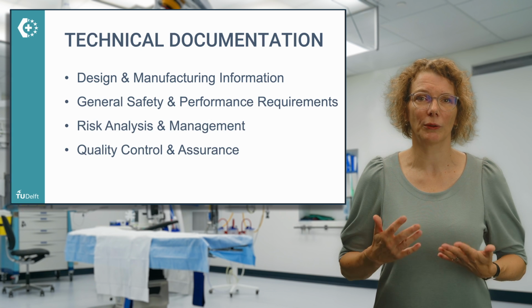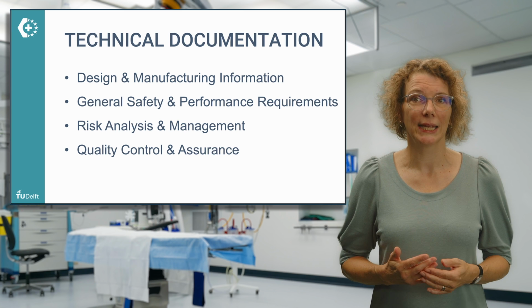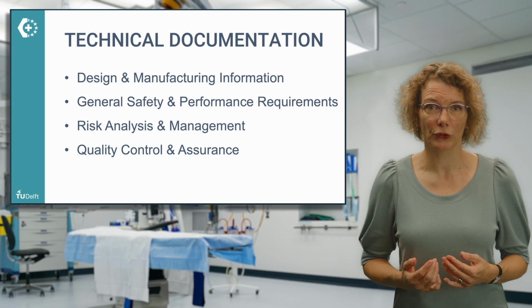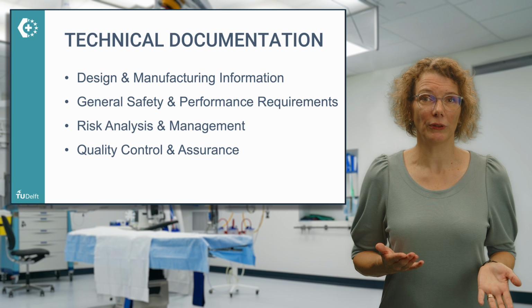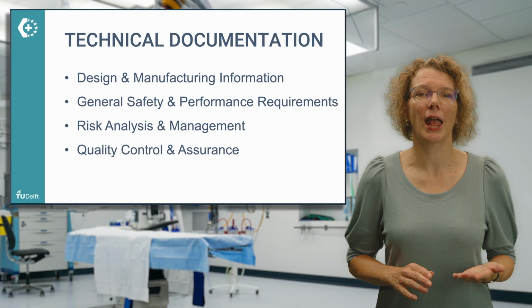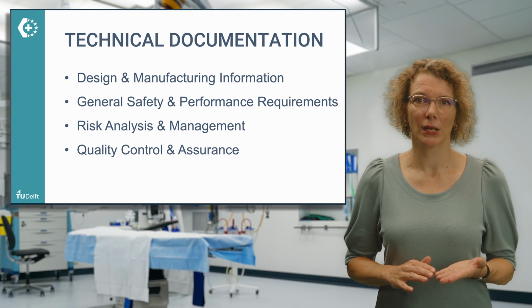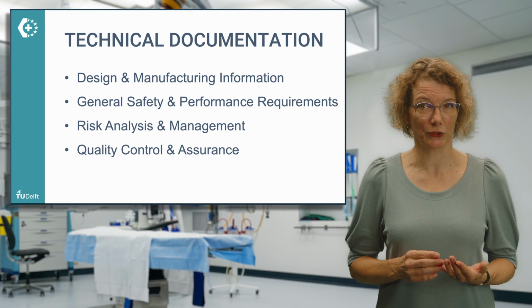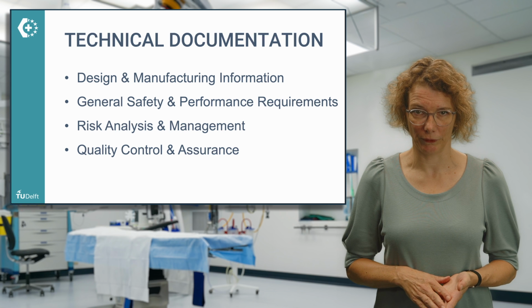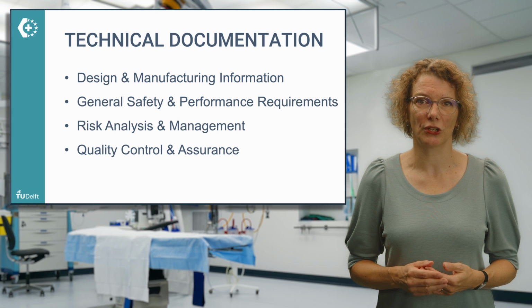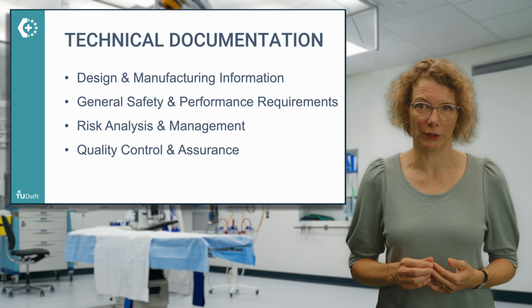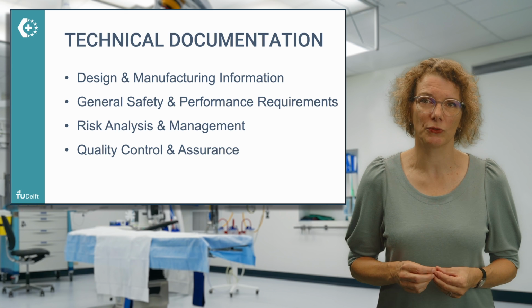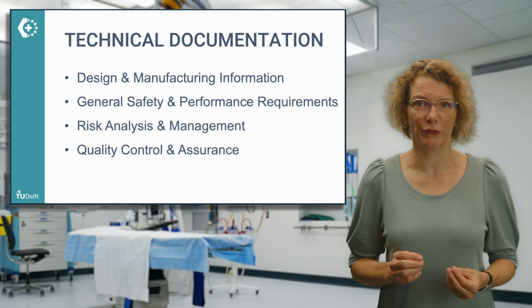It also includes the general safety and performance requirements, the implemented risk management approach, the quality control measures throughout the design and manufacturing process, and the final product testing. Manufacturing sites should be stated, as well as suppliers and subcontractors involved in the design and production. These technical documentation sections are strongly connected with each other and are essential for demonstration of conformity with the medical device regulations.